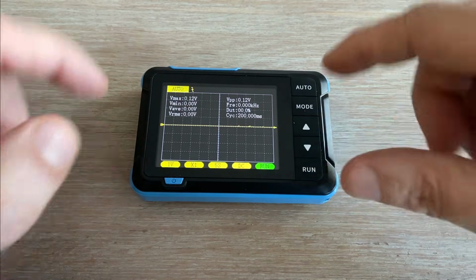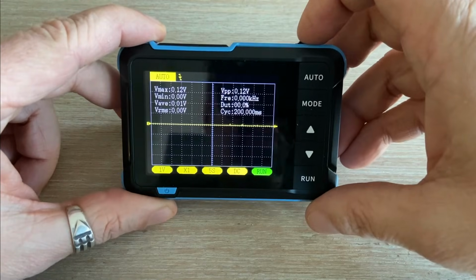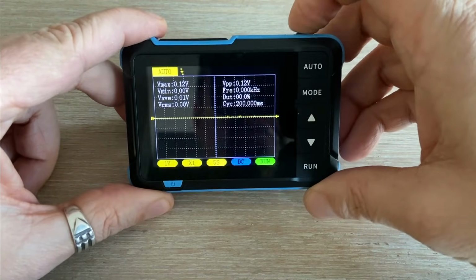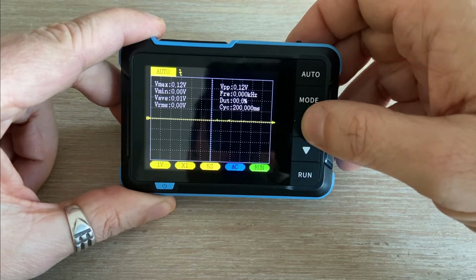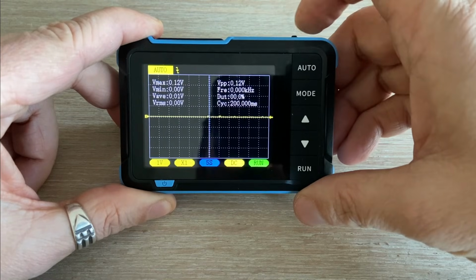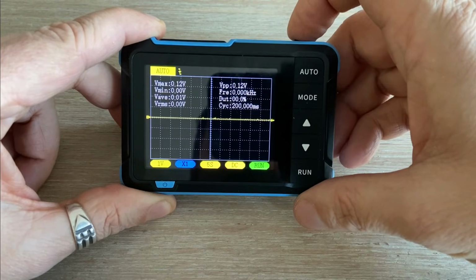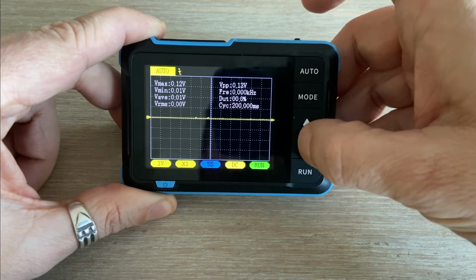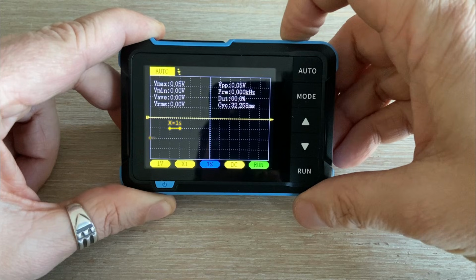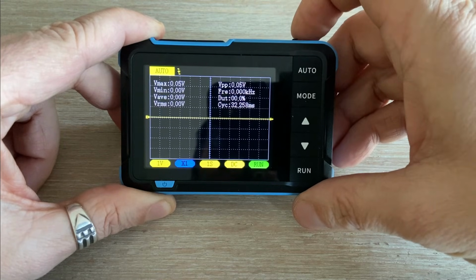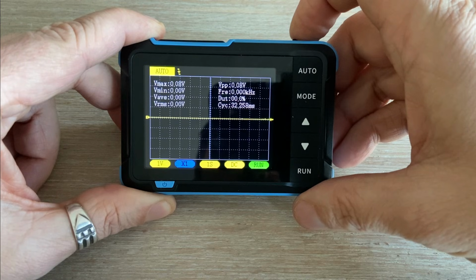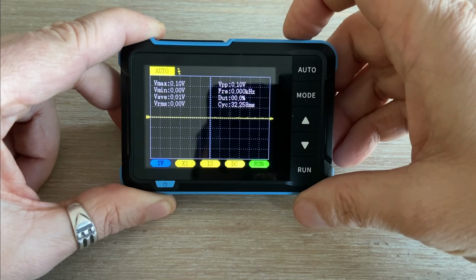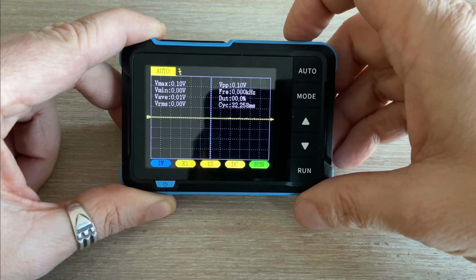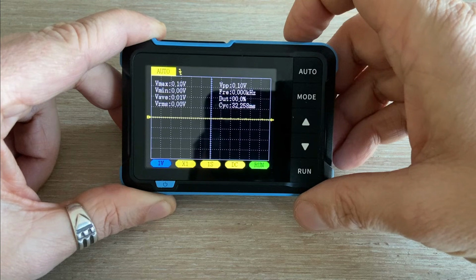At the bottom of the screen you will see the parameters you can adjust to control how the signal is displayed. You select and adjust them using this parameter select knob. For example, you can measure either AC or DC voltage. For this demonstration I will stick with DC. The next parameter is the time scale, which determines how much time each horizontal grid square represents. In this case we capture 12 times 1 second, giving us a 12-second signal window. Next is the multiplier setting. If the signal is very weak, you can amplify it 10 times. I won't use it for this demonstration. Finally, we have the voltage scale, which defines how many volts each vertical grid square represents. Here we can capture plus minus 4 volts.